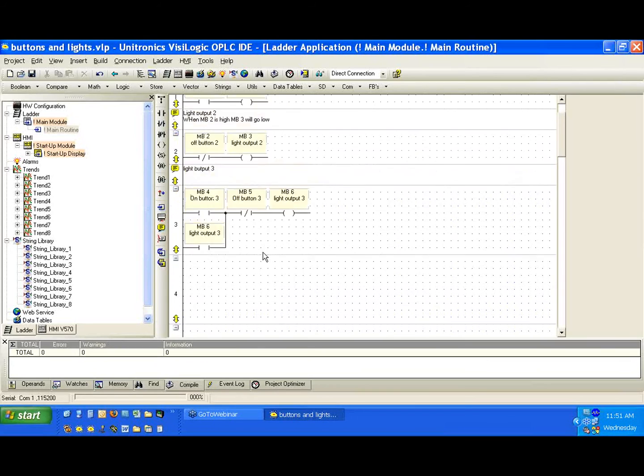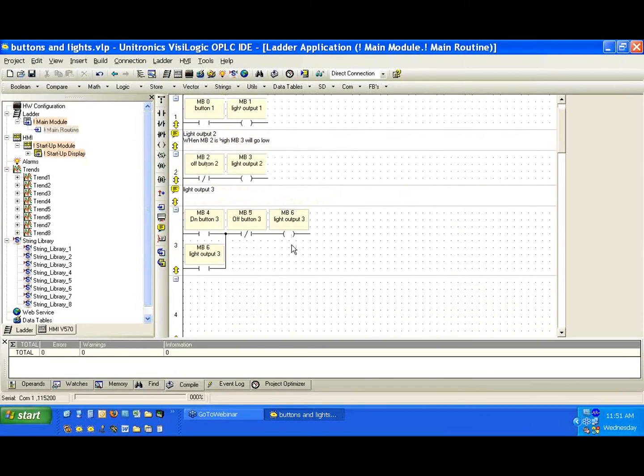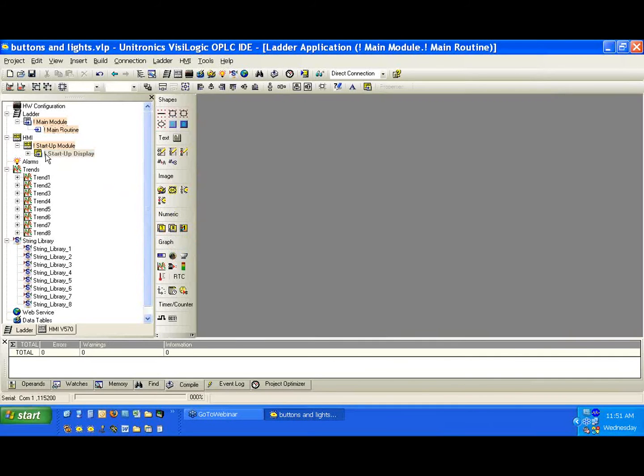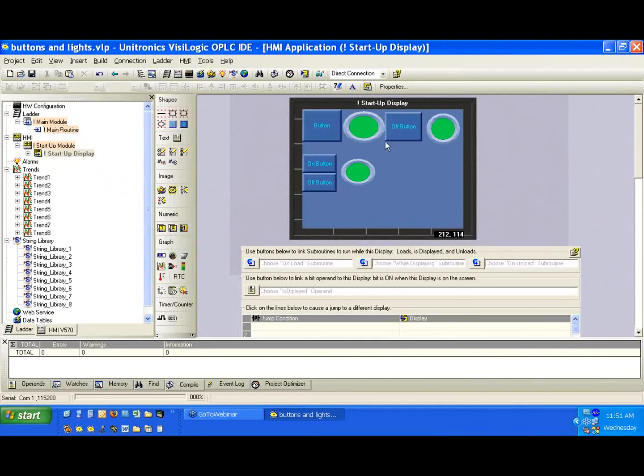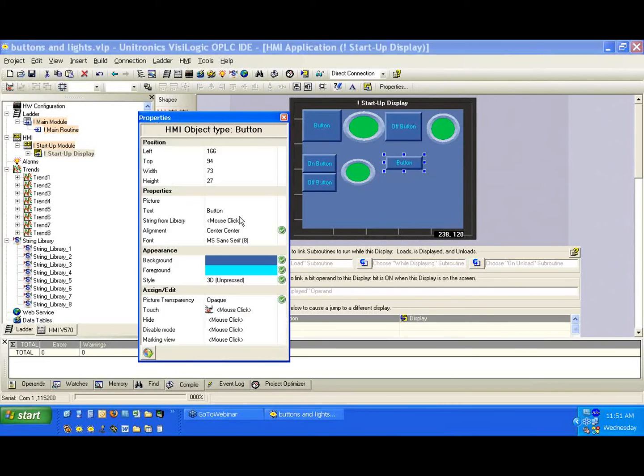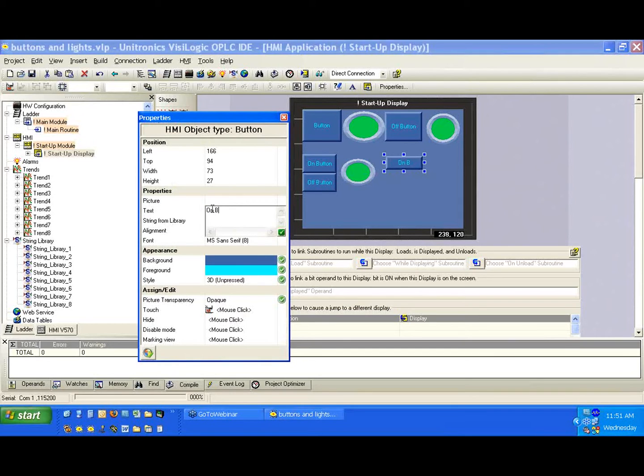This latch network was very popular before we had things like an enhanced operating system. Notice that we used the output, we set it back in as an input to keep its state high. It's a great idea, but what we can do now is use set and reset bits.